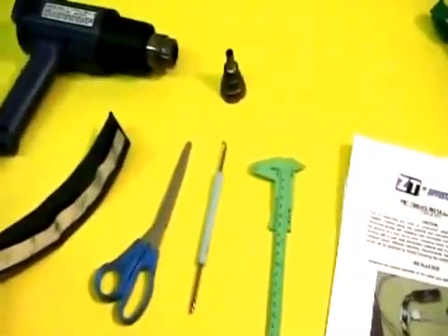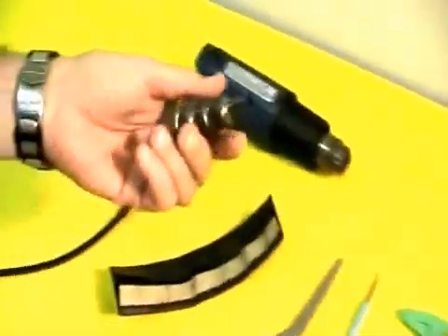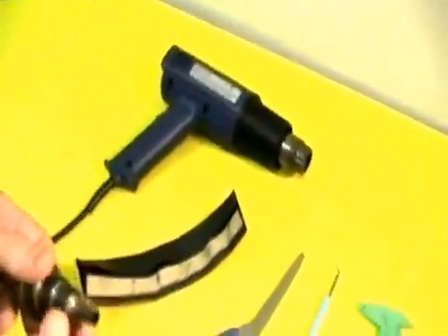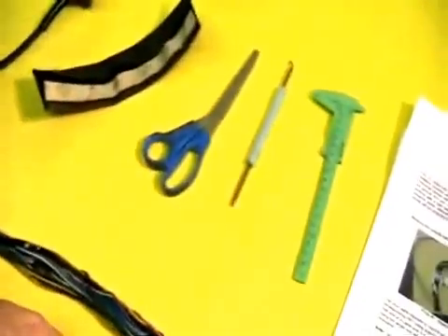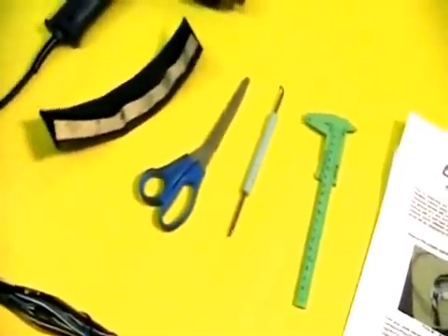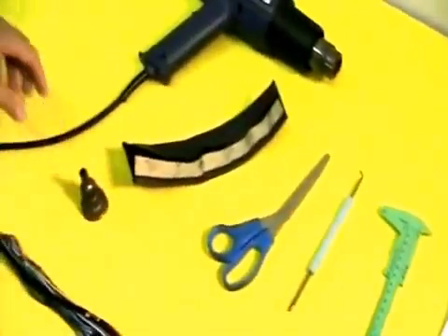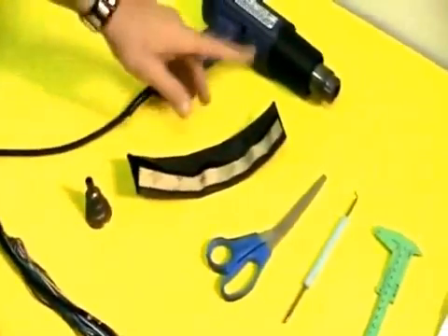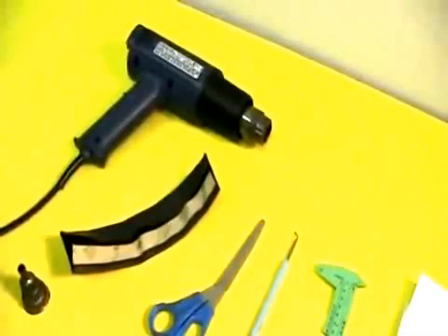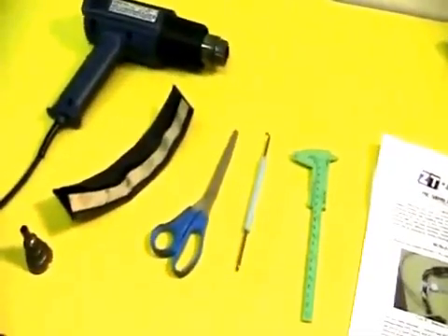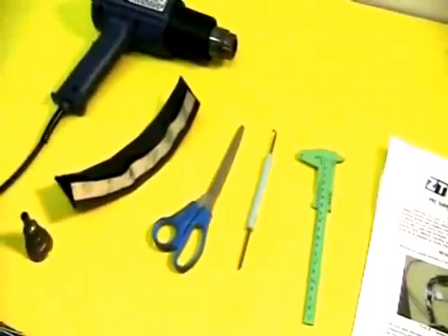You also will need a narrow nozzle type attachment for your heat gun, not a tubing reflector that is very common with heat shrink tubing, because one of the main differences of PRT is that you want to apply the heat selectively in the beginning to the adhesive overlap area. This sets the adhesive and the bond strength of the adhesive joint will approximately double upon cooling.